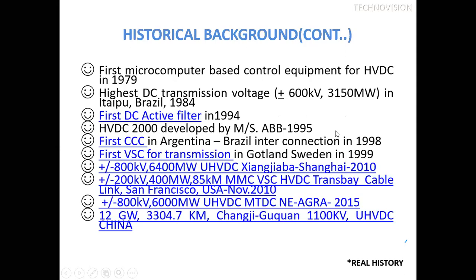In 1995, the HVDC 2000 concept was given by ABB. In that concept, they developed outdoor valves. Generally, we have thyristors indoor, but they developed outdoor valves, and the size of the valves was very small. They developed continuously tuned filters. To eliminate particular harmonics, we want a high pass filter, band pass filter, like that. But they developed a ConTune filter. ConTune means continuously tuned filter. So one single filter can take care of all the harmonics present in that HVDC system. So that concept was HVDC 2000.